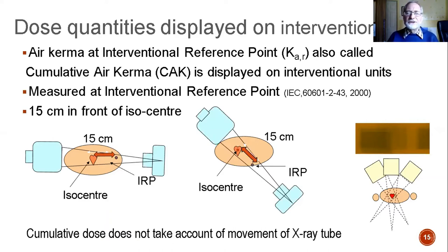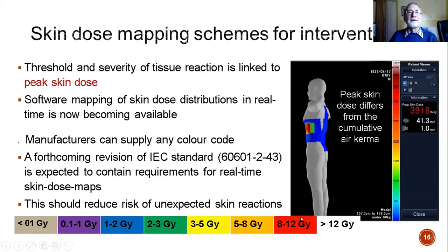The cumulative dose doesn't take account of the movement of the X-ray tube, so it's likely to be a bit higher than the peak skin dose, although it doesn't include the contributions from backscatter. Now, the threshold and severity of the tissue reaction is actually linked to the peak skin dose.